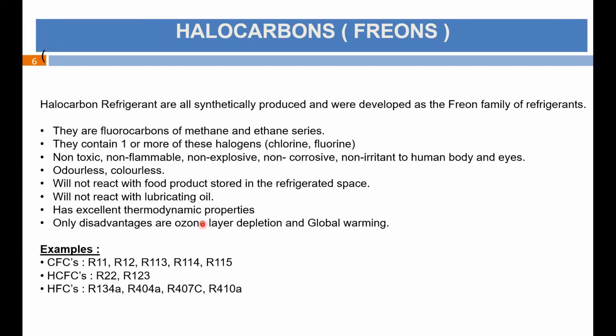These are non-toxic, non-flammable, non-explosive, non-corrosive, non-irritant to the human body and eyes, odorless, colorless. And the good part is that they will not react to the food products stored in the refrigerated space. Good for the refrigeration process. Will not react to the lubricating oil. Many of the refrigerants are quite miscible with compressor oil. Many of them have very excellent thermodynamic properties. The only disadvantages of these Freon refrigerants are ozone layer depletion and global warming. I'll come to full details of what ozone layer depletion and global warming are. So these are the examples I've already touched upon: CFC, HCFC, and HFC. These are all halocarbons.